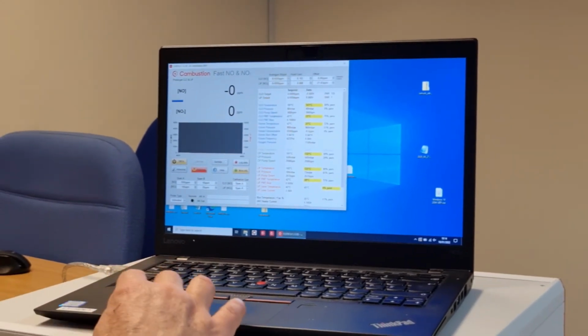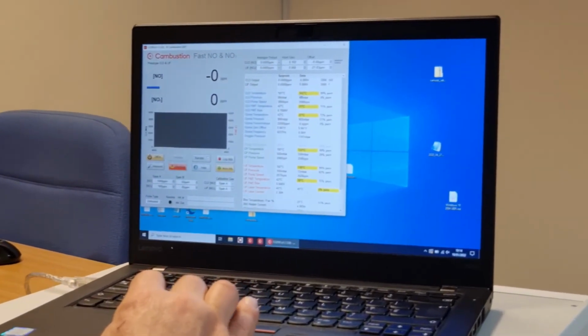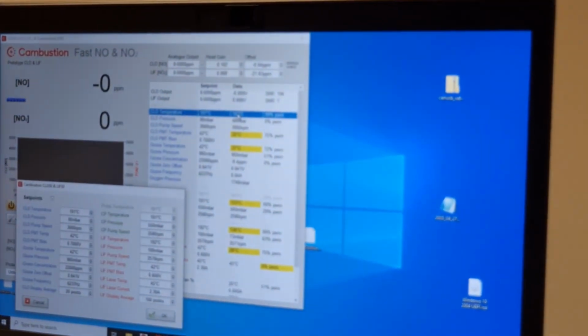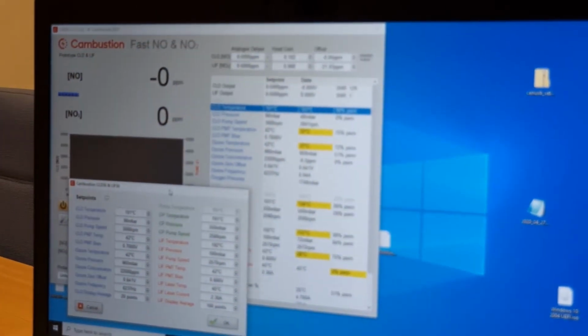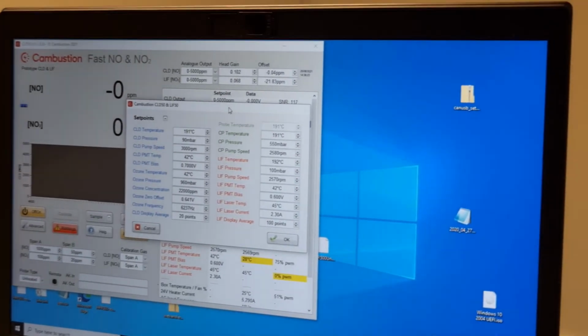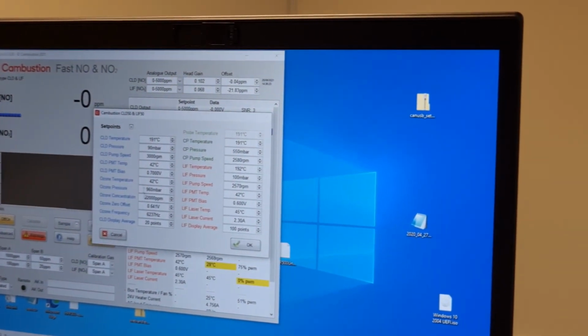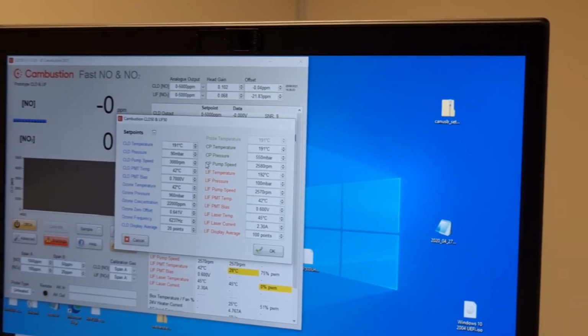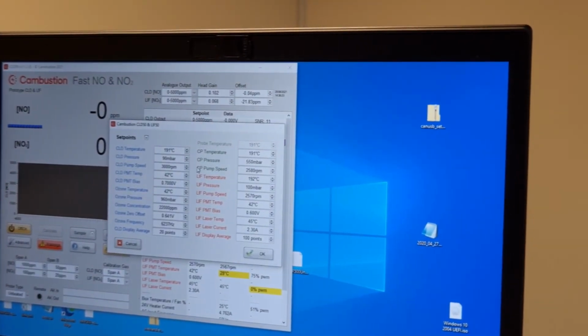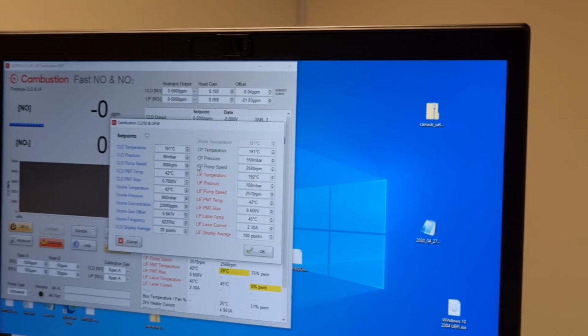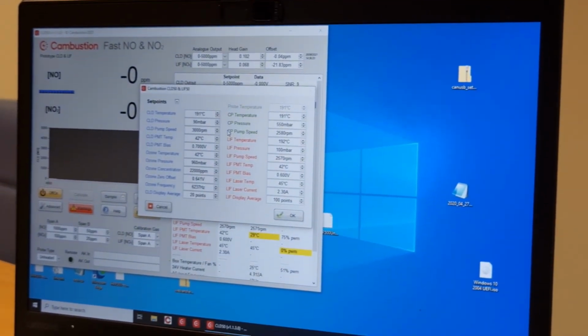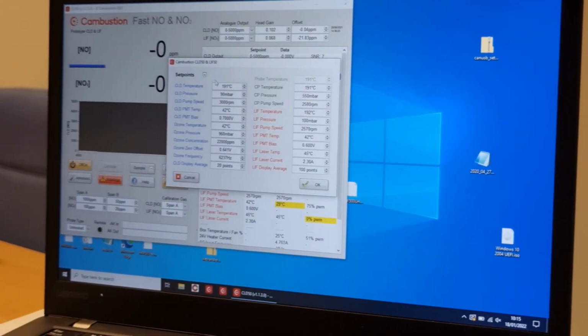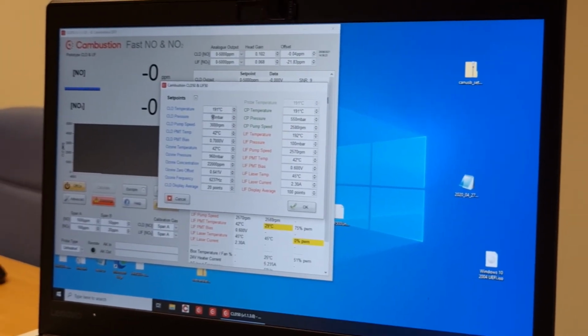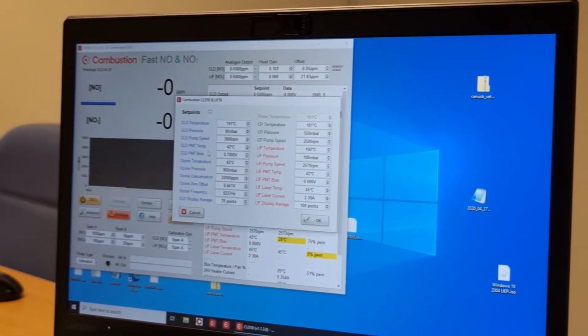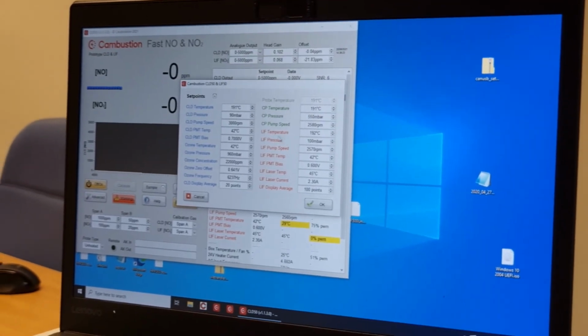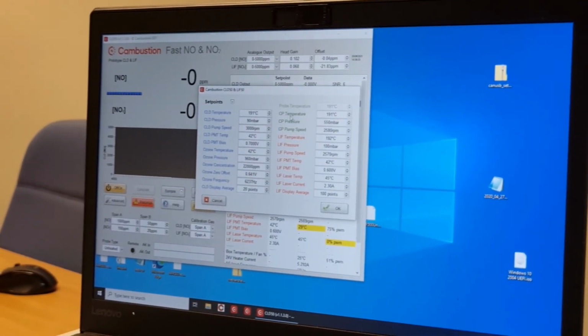I'll now show you the set points, because if you double click anywhere within the head info window, you'll pull up a number of set points. So there's a lot in here that you probably won't need to adjust, but we may, with some technical support, ask you to adjust some of these. There are a number of parameters in here grouped together in blue, applying to the NO CLD, in red for the NO2 LIF, and in green, common to both.